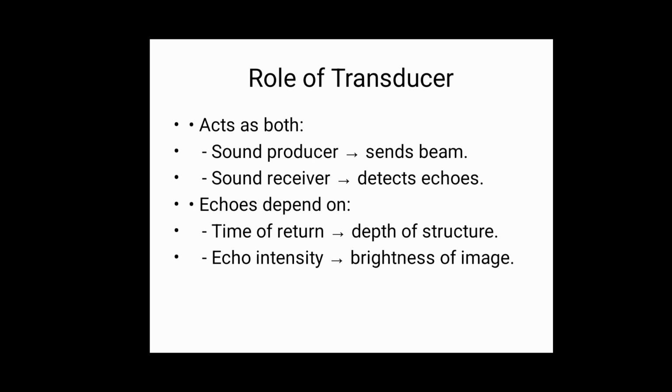Ultrasound images are obtained by using a pulse echo technique with the transducer serving as both a sound producer and sound receiver. A brief microsecond pulse of ultrasound energy is directed into the patient. The transducer then becomes a receiver, detecting ultrasound beam echoes reflected back to the transducer from tissue in the patient.